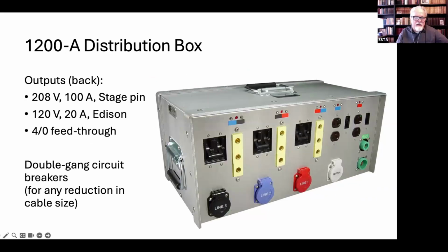All right. So then flipping that box around, there are 3 yellow outlets. So yellow is kind of an unofficial color code for 208 or 240, something in the upper range of voltage. And you'll notice that each one of these connectors has a circuit breaker. The circuit breaker is a double gang circuit breaker. So if we're plugging an 18K into this, let's say that's 96 amps per phase, this one on the left would be taking 96 amps from blue and 96 amps from black. It's dividing the load between those 2 phases.